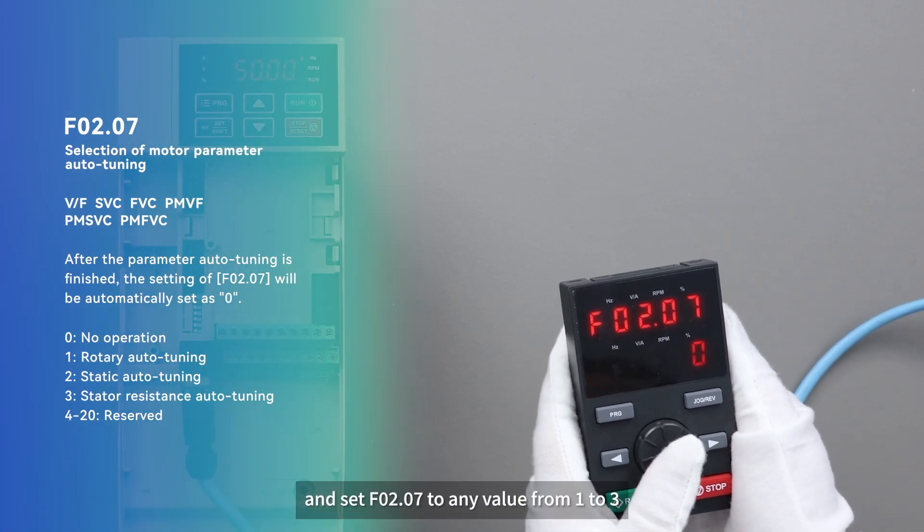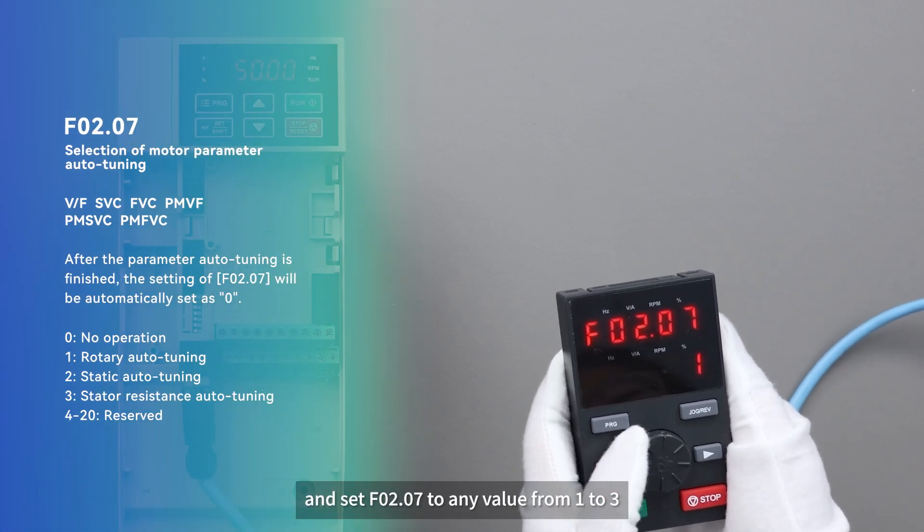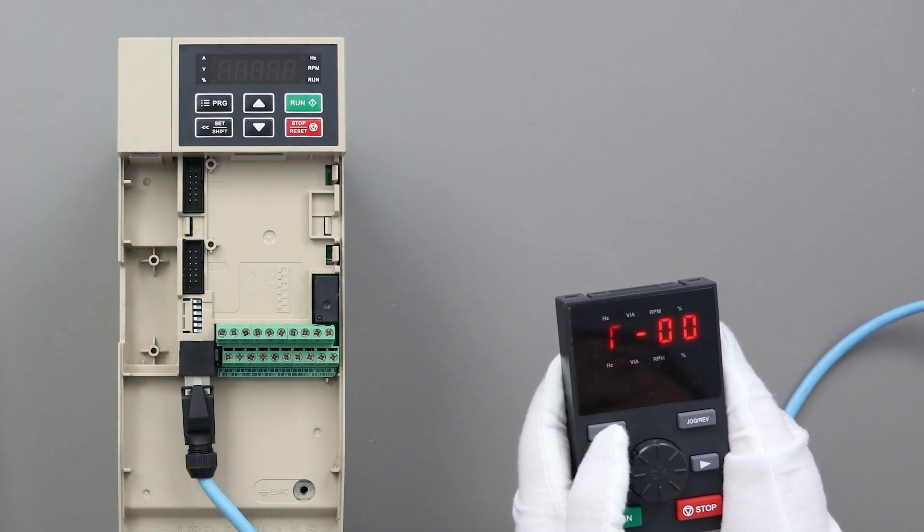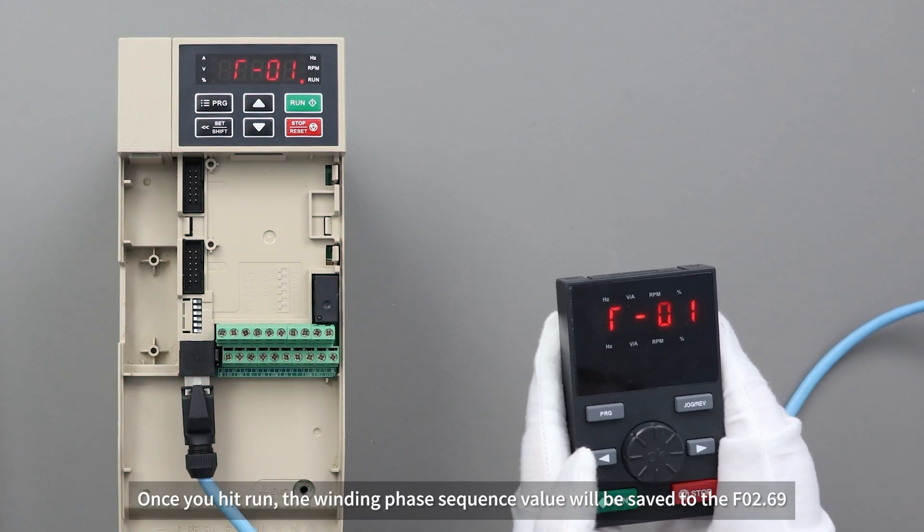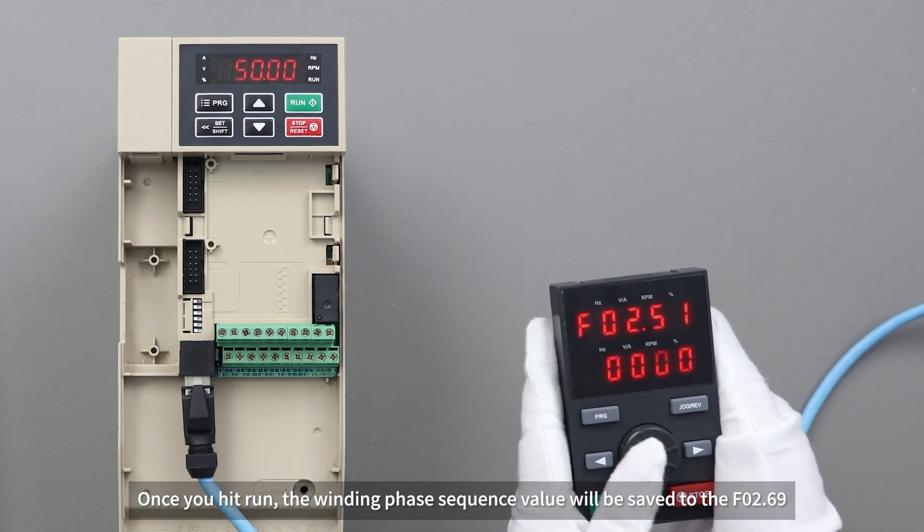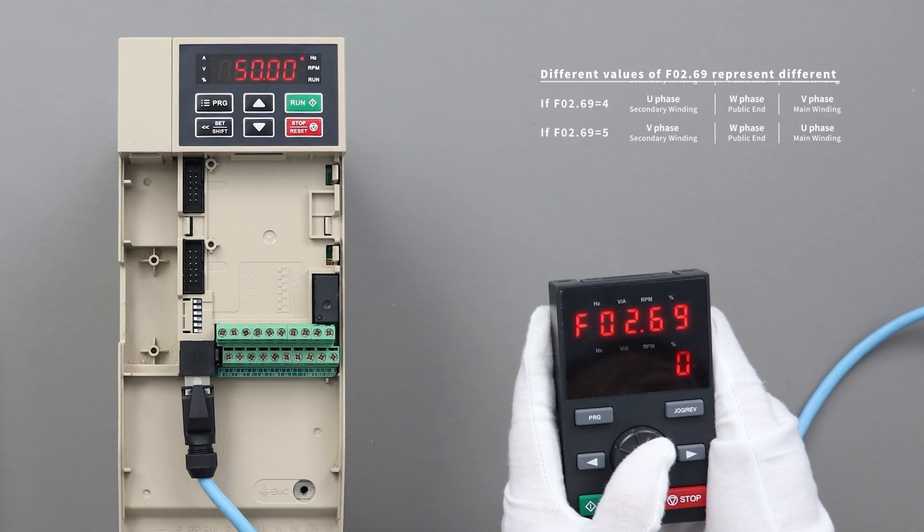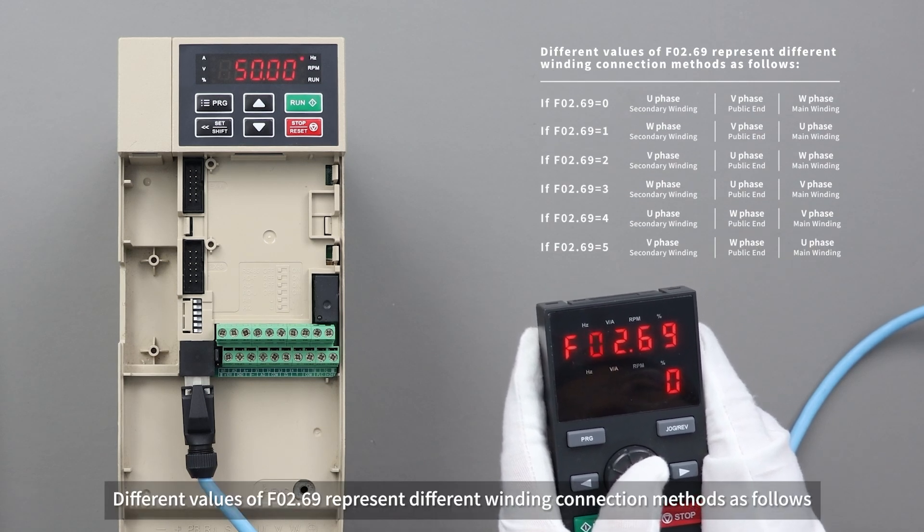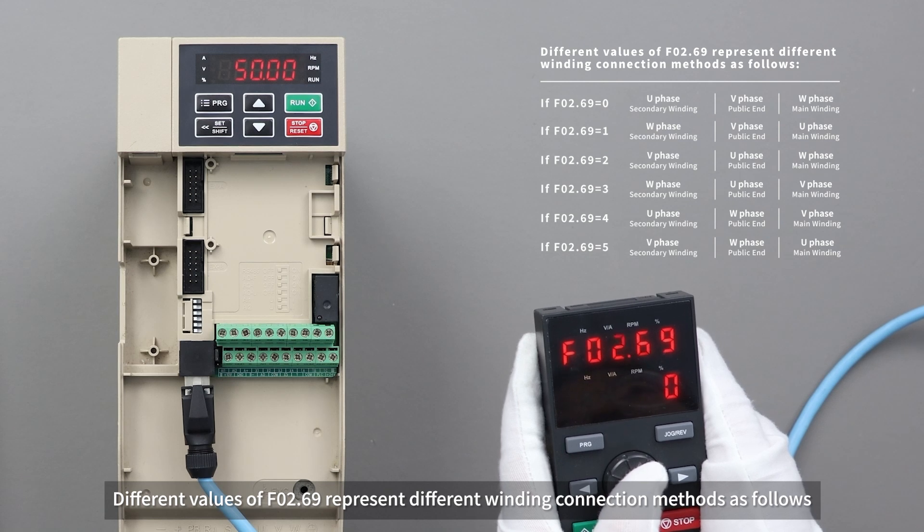And set F02.07 to any value from 1 to 3. Once you hit Run, the winding phase sequence value will be saved to F02.69, which defaults to 0. Different values of F02.69 represent different winding connection methods.